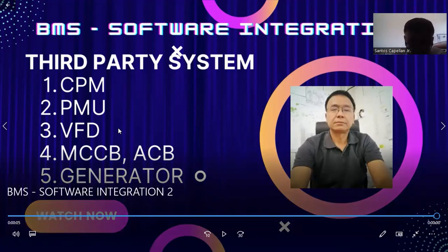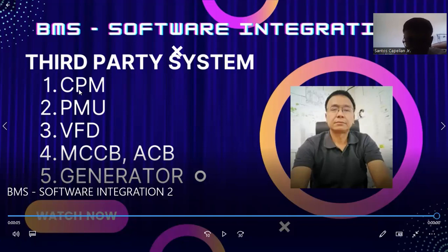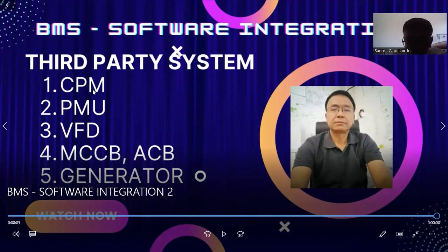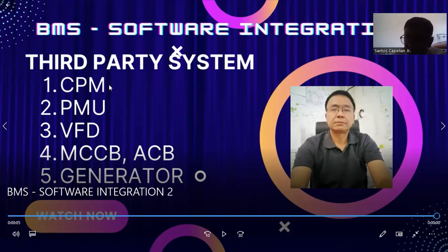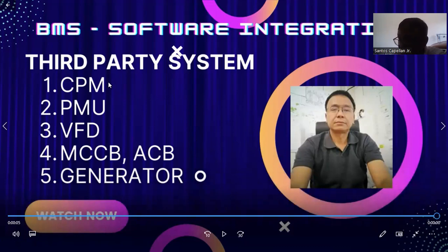What is important is you need to have a good relationship with the supplier of the third-party system. For example, the CPM — the Chiller Plant Manager — the supplier will supply the chillers and also the DDC panel or chiller plant manager system that controls the entire operation. If the CPM's communication protocol is BACnet over IP, you will be doing software integration through BACnet over IP, which is very easy to do.